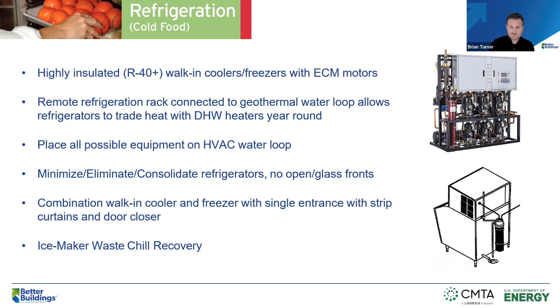Quick little anecdote, again, back to Richardsville Elementary School. About 6 months after that project opened, we did a post-occupancy walk just to kind of see what was working and what wasn't, and how the building was being used. So again, this is a school that performed at an 18 EUI. And one thing that we noticed was there was a very old Good Humor ice cream cooler plugged in the kitchen by the serving line. And it was visibly very old, didn't seem to shut off while we were there. So I put a kilowatt meter on it and left it on for a couple hours while we were there and checked it before we left. And was able to confirm that the compressors in that unit never turned off, not once.